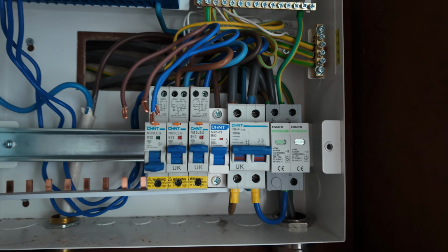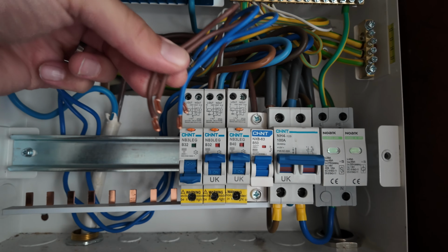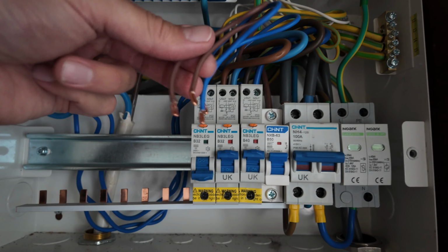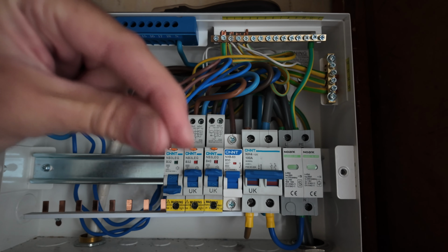Yeah, basically, you would expect the resistances between the lives and the neutrals to be the same because the lives take the exact same path that the neutrals do because obviously they're in the same cabling together. So you expect them to be exactly the same. We do this with the earths as well. I'm not looking into the earths too much at the minute. I just want to get an idea of what's happening. So next thing I'm going to do is I'm going to plug the kitchen area now.